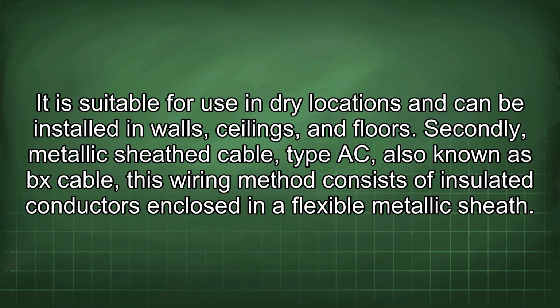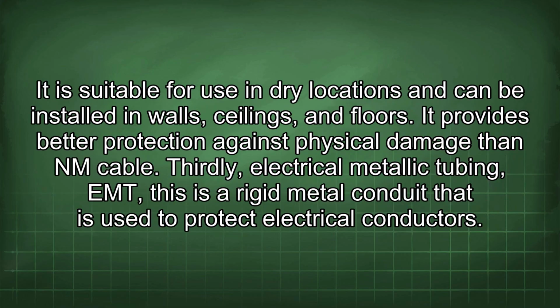Secondly, metallic sheath cable, type AC, also known as BX cable. This wiring method consists of insulated conductors enclosed in a flexible metallic sheath. It is suitable for use in dry locations and can be installed in walls, ceilings, and floors. It provides better protection against physical damage than NM cable.